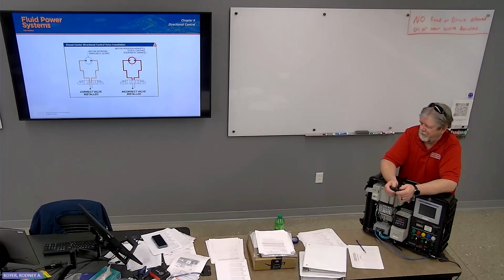Depends on what you're doing. By definition, emergency stop is all motion stops. But it depends on what is the lesser of two evils. You know, if I need to stop it immediately right now, then I'm going to use the one on the right-hand side. If I need to stop it within, you know, a couple of seconds versus right now, I'm probably going to use the one on the left-hand side and then put an external brake on it that I can engage.